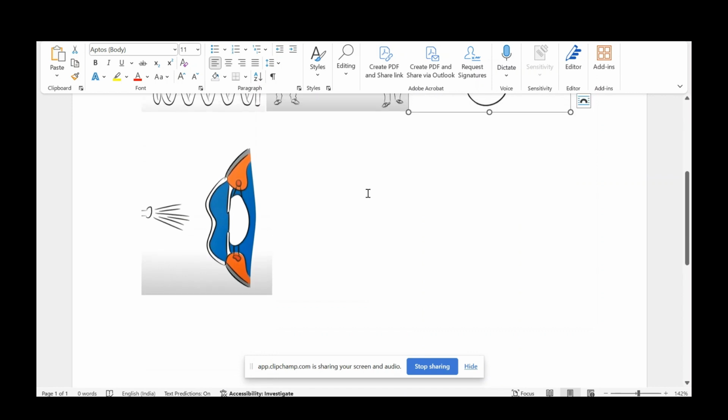In corneal biomechanics, for example, the Corvis ST, a machine from Oculus, who are also the makers of Pentacam, sends an air pulse to deform the cornea and measures how much it is indented at first, how quickly it takes back its original shape, and how much time it takes.